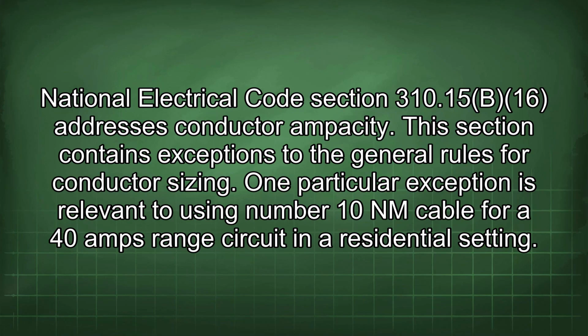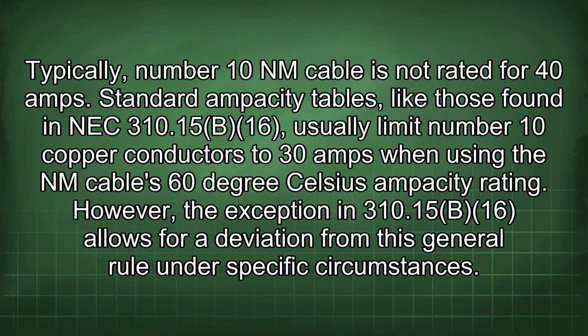National Electrical Code Section 310.15(B)(16) addresses conductor ampacity. This section contains exceptions to the general rules for conductor sizing. One particular exception is relevant to using number 10 NM cable for a 40 amp range circuit in a residential setting. Typically, number 10 NM cable is not rated for 40 amps.